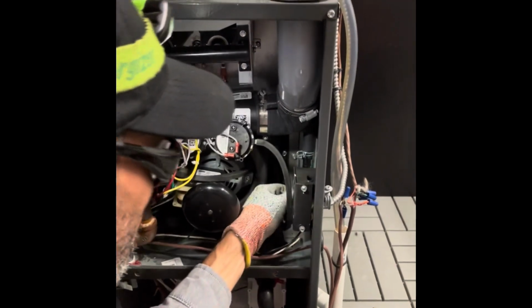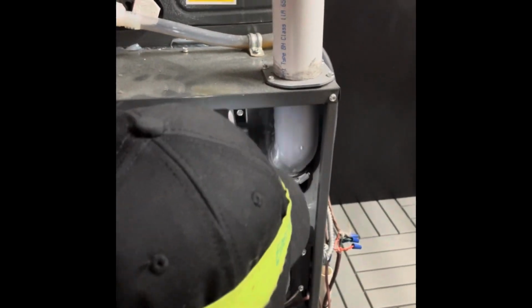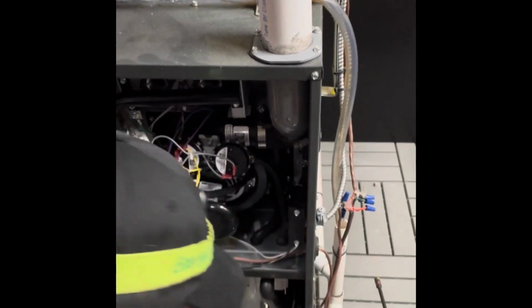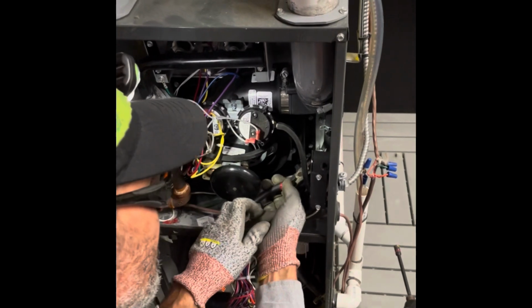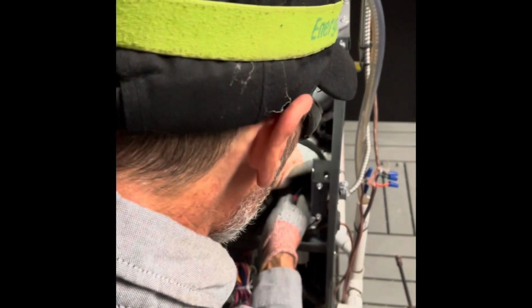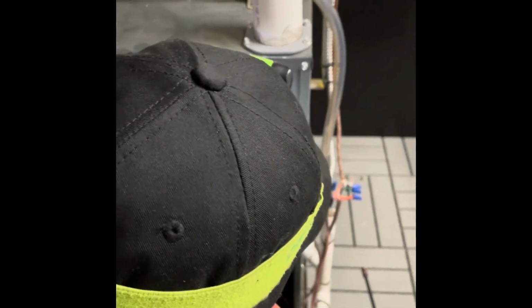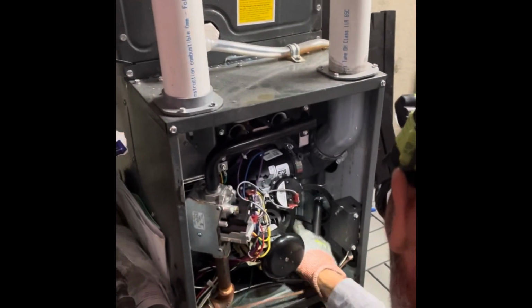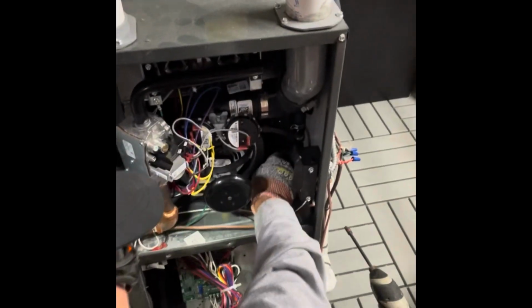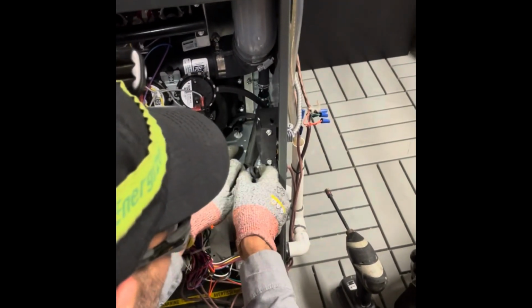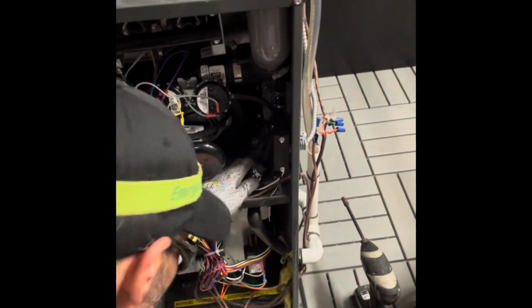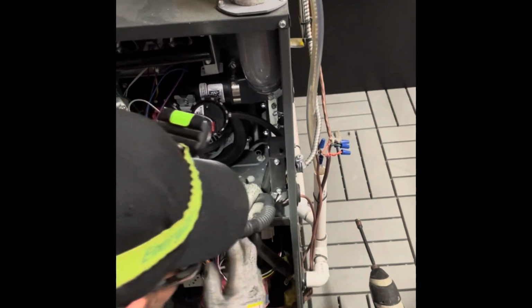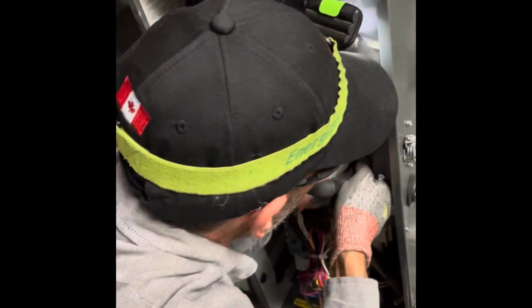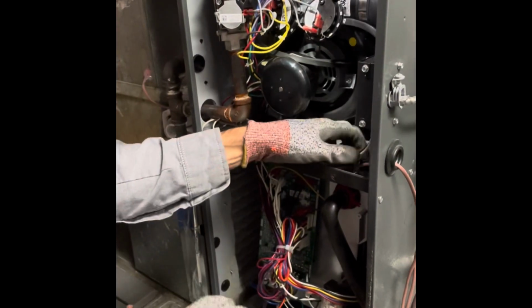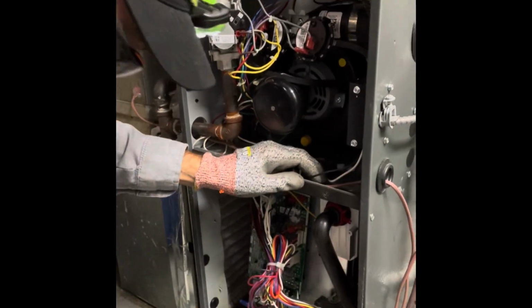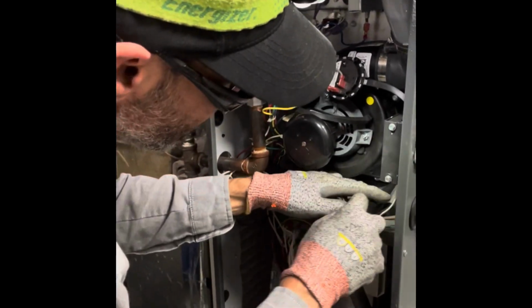Alright, so I confirm both of those hoses are clear, the fitting itself and the hose going down to the trap. So I will put this clamp back in place so that we don't get any water leaking. Alright, and then I'm just going to remove this clamp on the right side corner, bottom of this collector box. And exact same thing, I want to blow some air in this little tiny hose. Make sure it's cleared out. Okay, so that one's clear, and I just want to put this other hose on that fitting and make sure it's not plugged up as well.